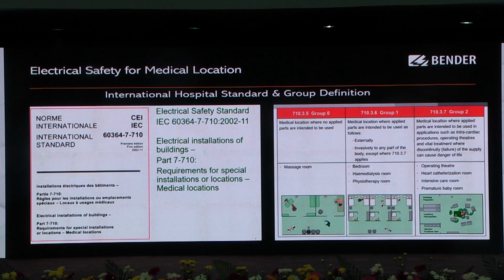There are also 2 types of residual current monitoring. You have to use type A or type B. You have to decide. Gopakumar sir has already informed about type A and type B CT. Type B CT is available in the Bender product. We are already providing it for hospital group 0 and group 1 locations. It is not an RCD; we are measuring with the type B CT at 2000 Hz frequency up to the 40th harmonics. Wherever a data center is there, even in a grounded system, in the PDU racks, we can supply residual current monitoring with the type B CT.